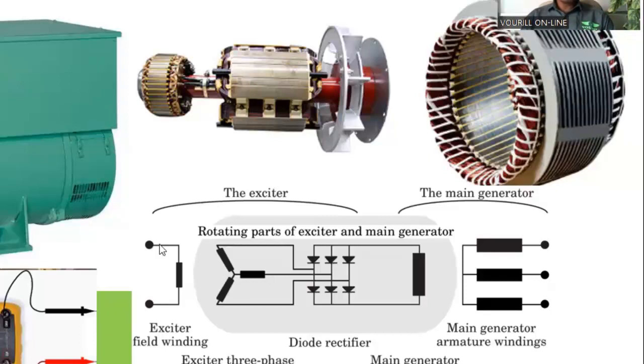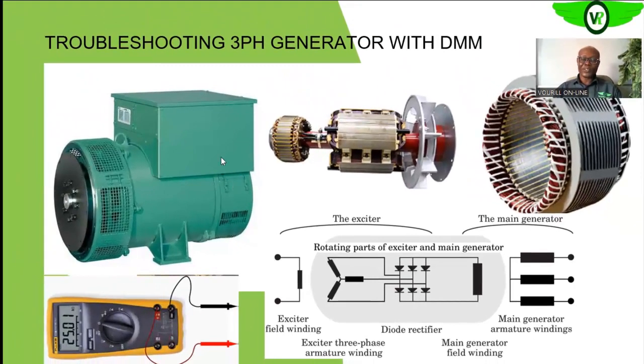Then you also have the exciter field winding. The exciter field winding is always on the stator, around the front of the housing that is coupled to the main stator housing, the exciter armature, and the generator main armature. So now the exciter field is here, and this is what is represented here now. These are the two terminals that are fed from the AVR.